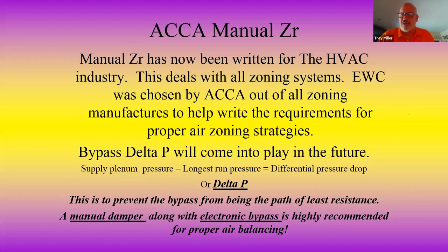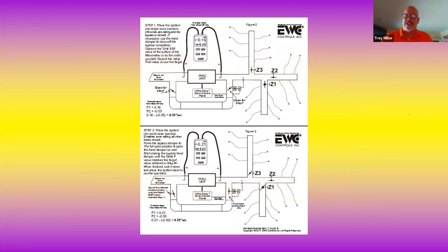But if you do, then you have to use a hand damper, and let me show you how we did that. We go right here. This is what I used to have to train on. I have to teach guys how to use a digital manometer. Basically, what I'm doing is I'm putting my two pitot tubes in. Instead of hooking them to my electronic bypass, I'm going to tie them to a manometer. I'm going to cut the system on with all zones open, make sure I'm in high fan speed. Then I'm going to check my static pressure. As you see here, we're at a 0.51 static. We've got a good duct system there.